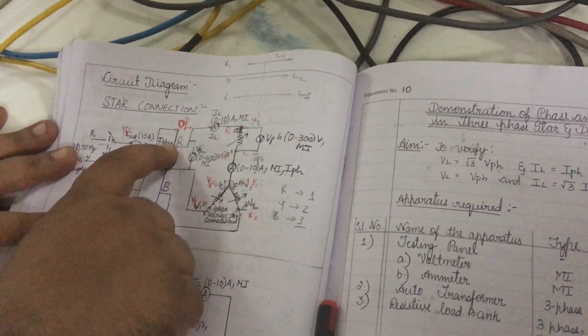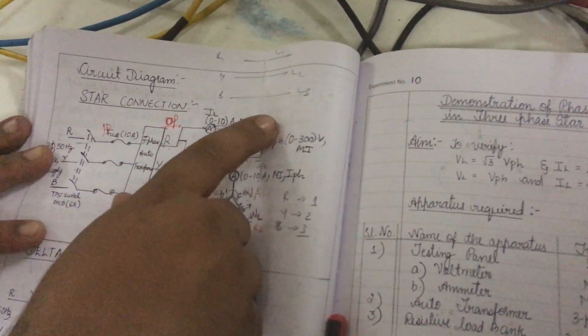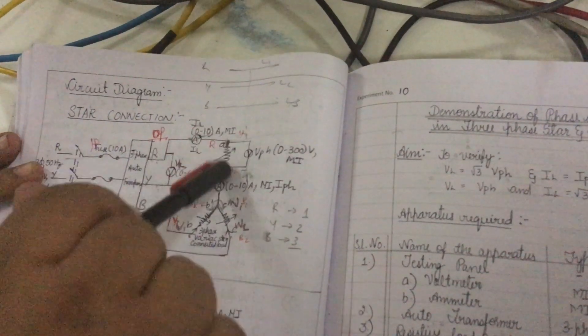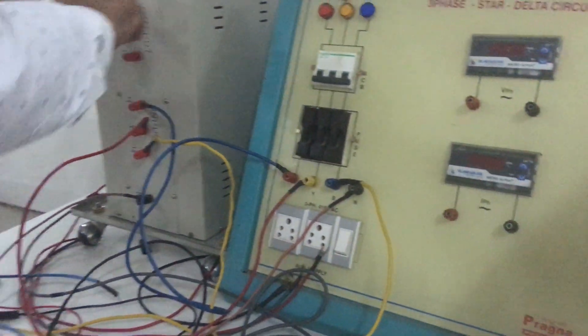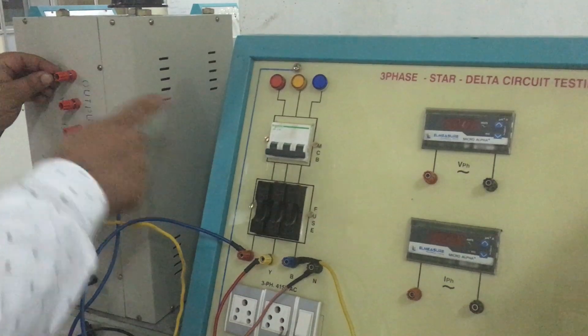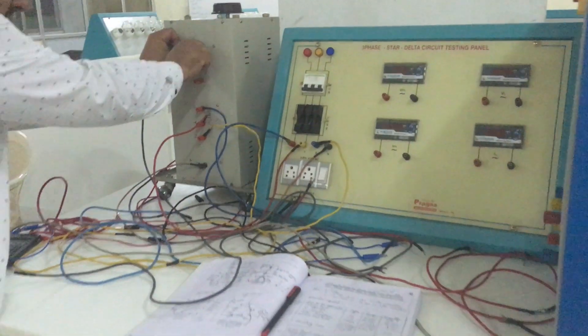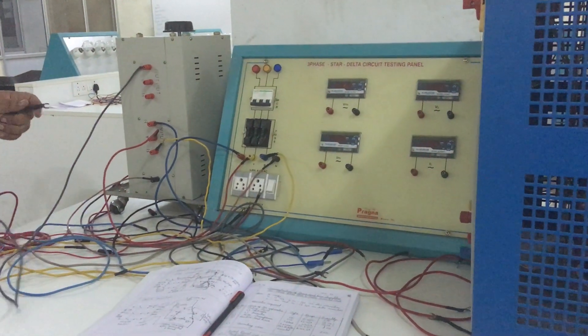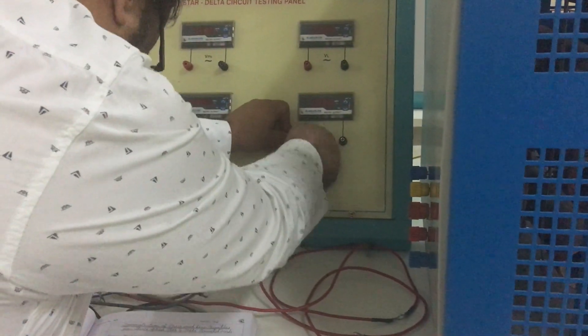The R connection goes to the line ammeter first. The other end of the line ammeter connects to U1 and U2, which is the red R color terminal. Be careful — a short circuit between U1 and U2 would be wrong. As per the circuit diagram, take R and connect it to the line ammeter.